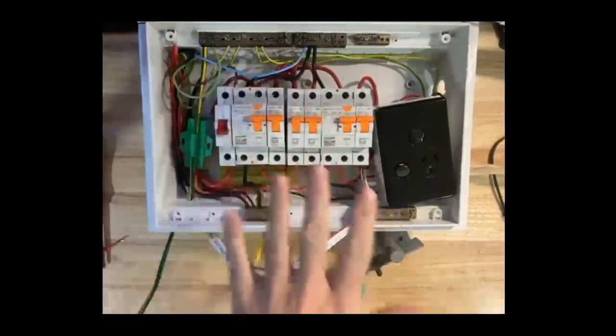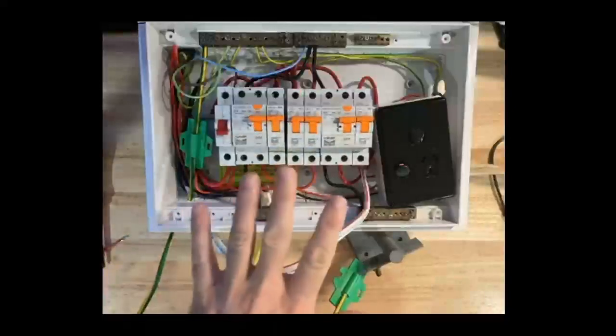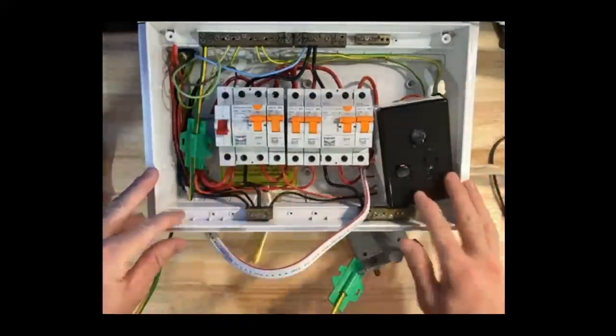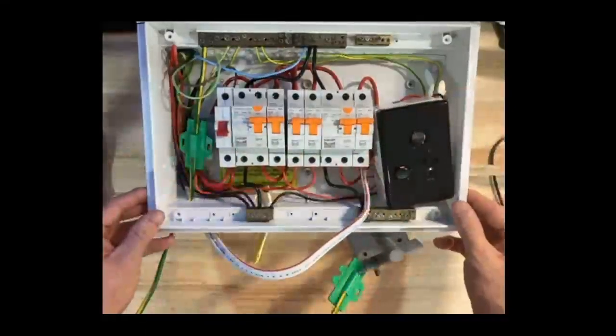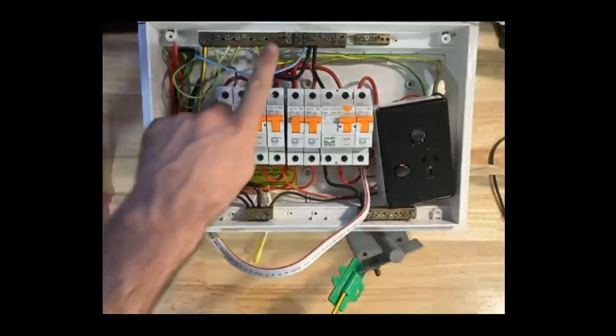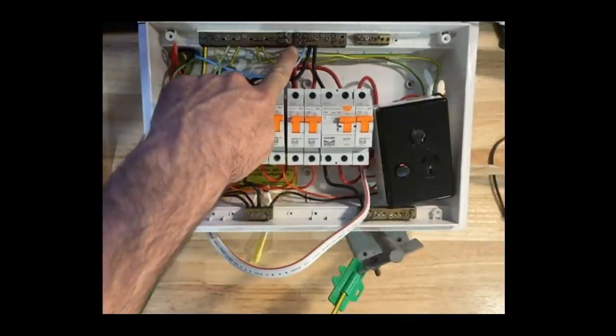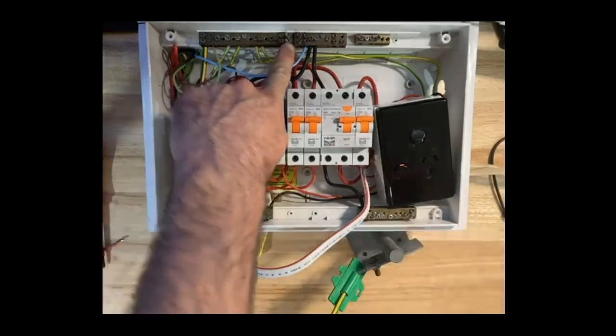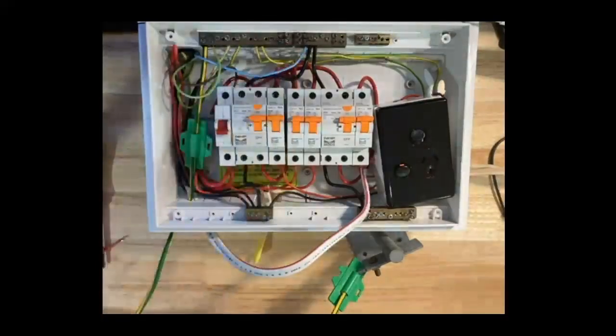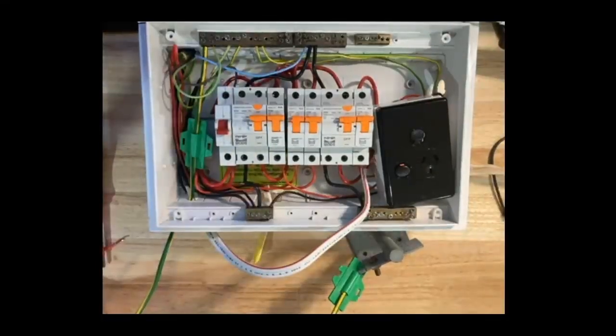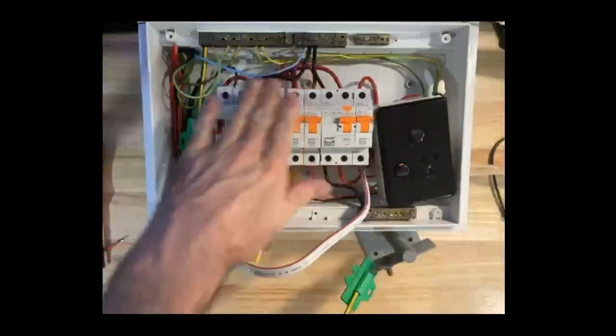So I have my switchboard here. A couple of points before we start. This switchboard is not currently connected to power. This is just freestanding on my desk. And you will note that I have removed the earth neutral link. The earth neutral link is not present. That is because I'm currently testing it and I've removed it for testing purposes. We should not generally ever need to remove the earthing link in a live installation. So please just note that I've done that for testing purposes.